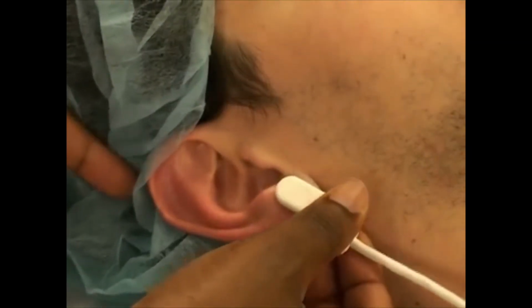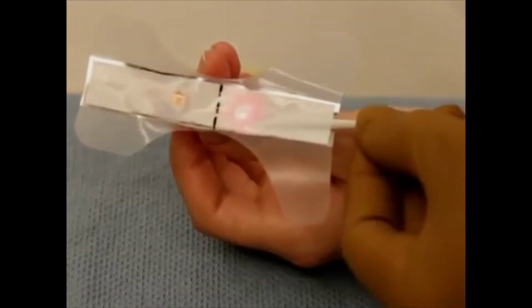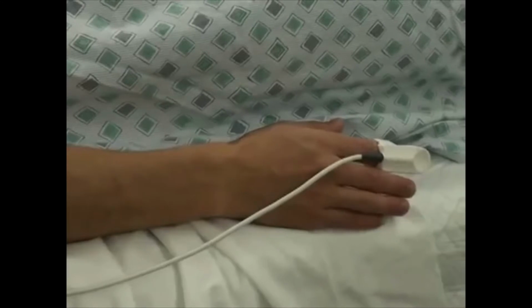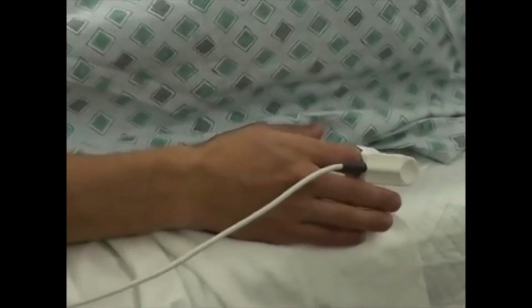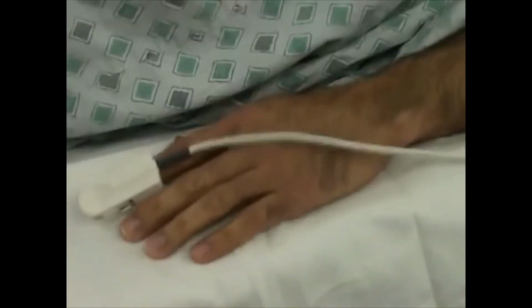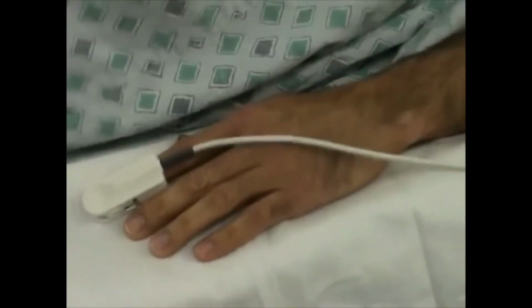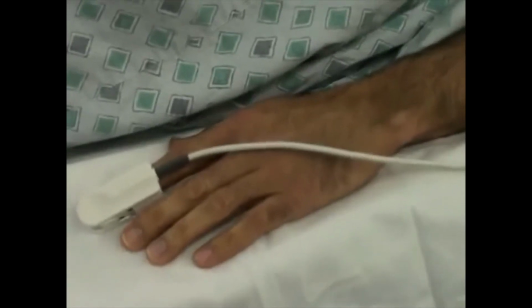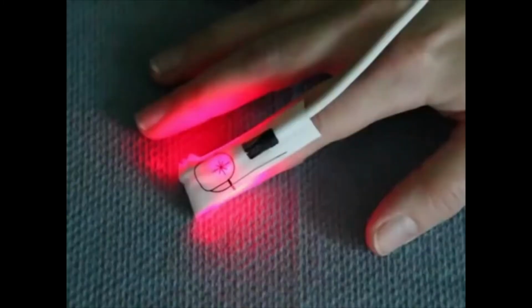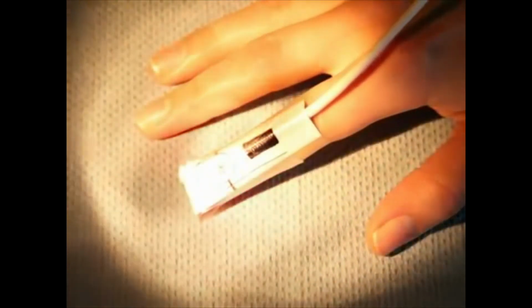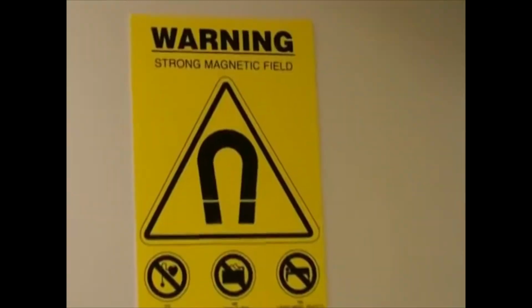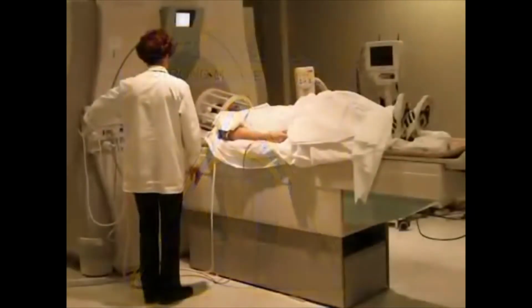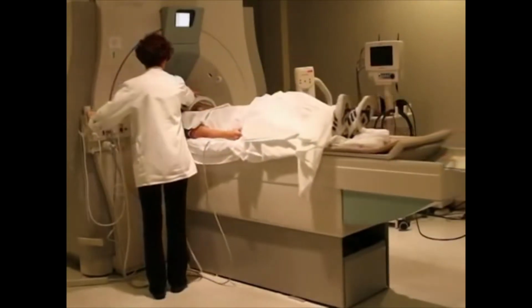Even though it is easy to use, the pulse oximeter can produce erroneous data in certain circumstances. One common problem is the occurrence of movement artifacts when there is movement at the site where the probe is placed. This may interfere with proper function and most often occurs if a patient is shivering, has seizures, or is being transported by ambulance or helicopter. The waveform of the pulse oximeter will be distorted in such circumstances, and the clinician should recognize that the measurement displayed is inaccurate. A bright light, such as an operating room lamp, may cause light interference, leading to an erroneous reading. Electromagnetic radiation, such as that emitted from an MRI scanner, may also interfere with pulse oximetry.